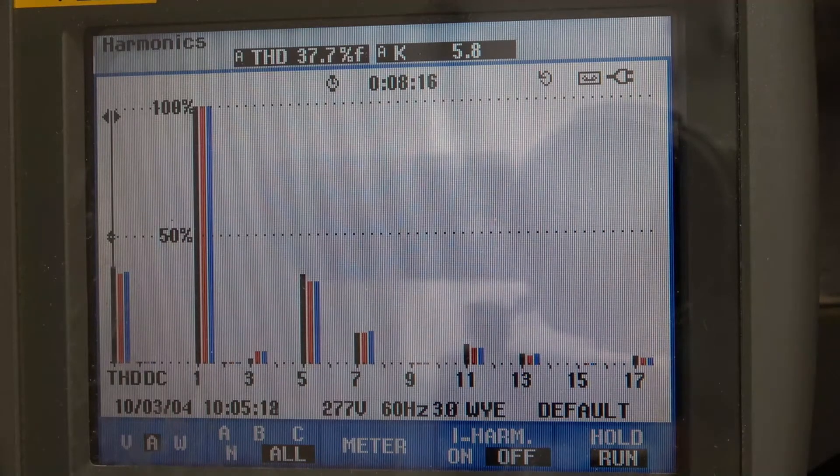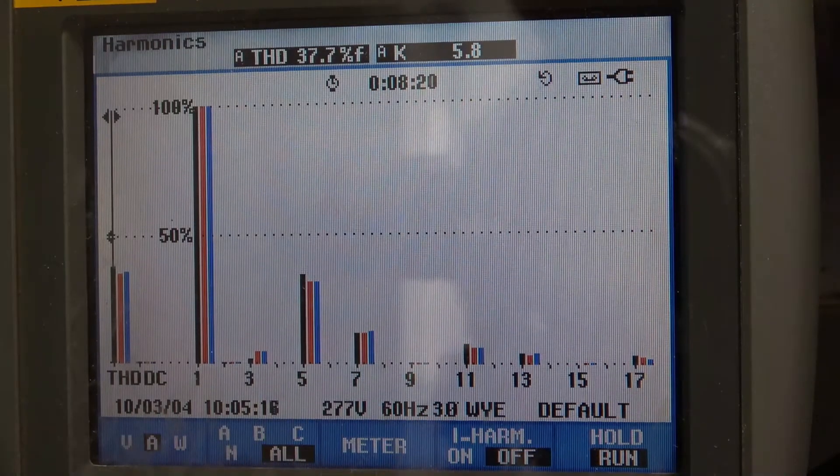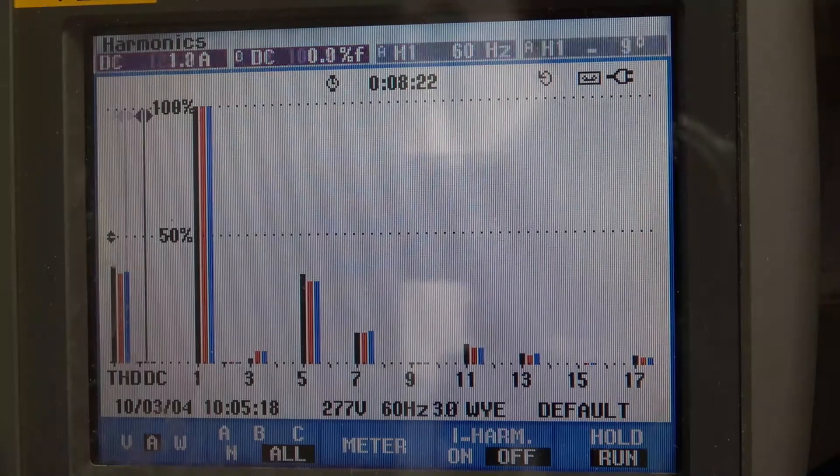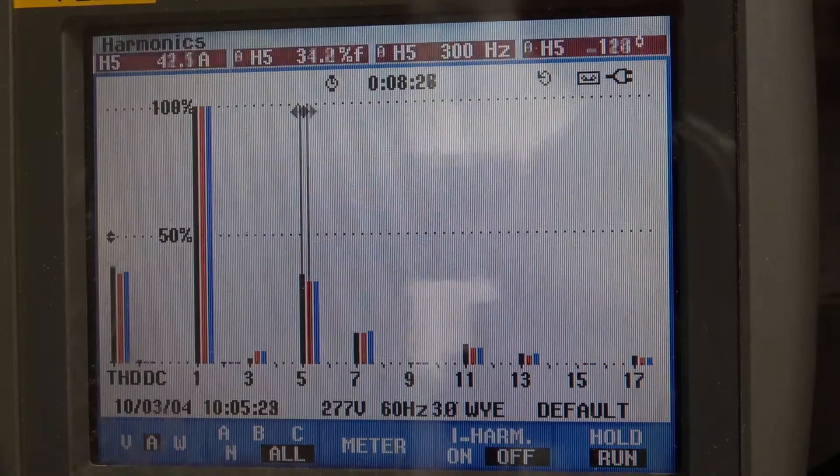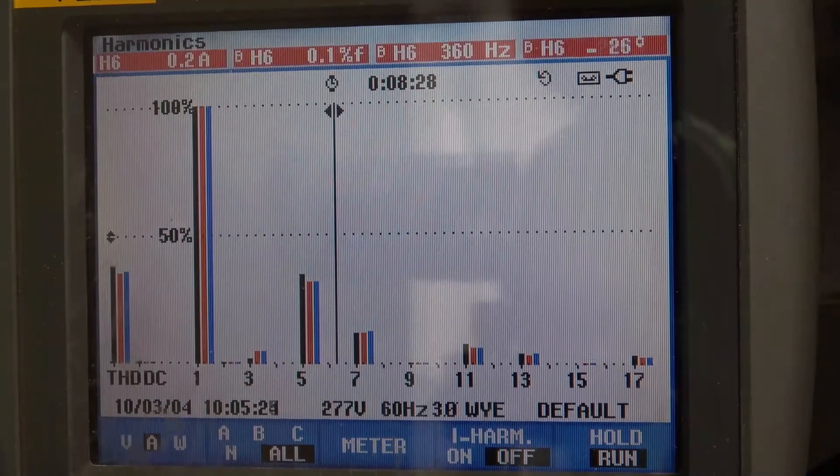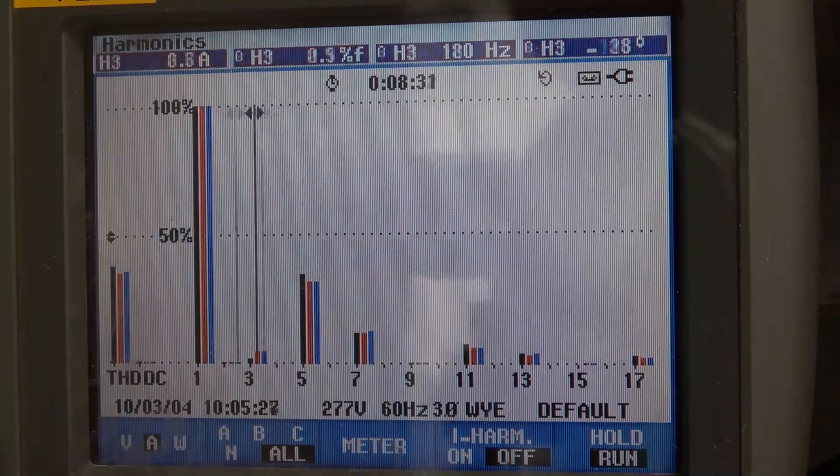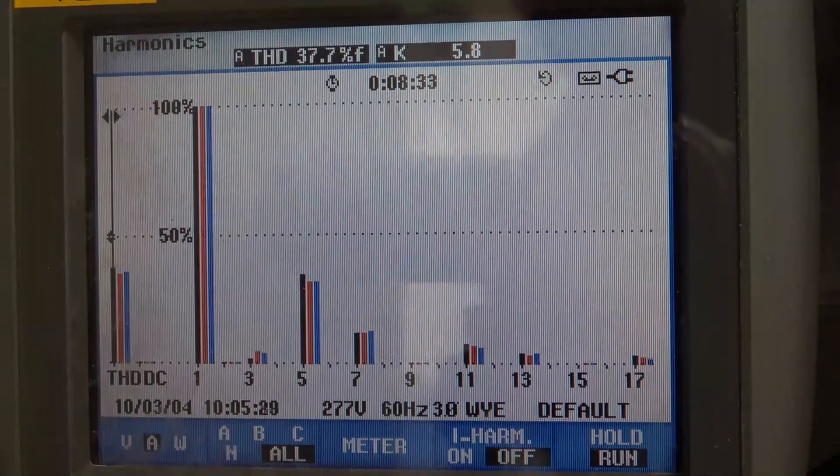So we have our typical six pulse drives. We have our 5th and 7th, 11th and 13th harmonic. For example, our 5th harmonic is here, 7th. So you can see a significant amount of harmonic current and our total harmonic distortion.